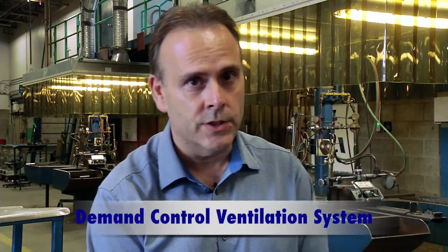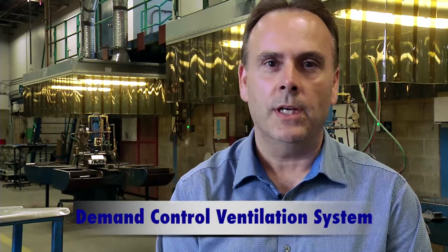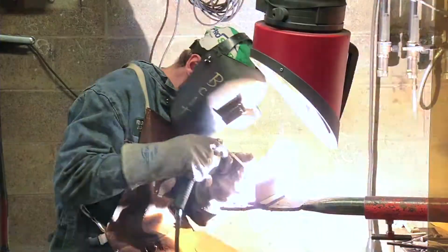The building had an existing ventilation system that was very inefficient. Essentially, it ran for 16 hours a day. The exhaust turned on, the makeup air unit turned on, and there really was no way to shut it off. It just ran all day long, and the idea was to introduce a demand control ventilation system. The welding booths themselves are not always occupied, and so the idea of the system is to only turn on the exhaust when a student is actually in the booth.